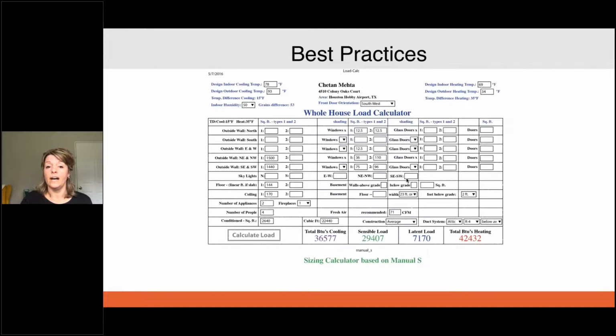So best practices for designing systems. We have our design indoor cooling temp and the outdoor temp, which is the peak load. So that design outdoor cooling temp is going to be the peak outdoor temperature that we're going to design our HVAC system around. And what's important to know about that is when we're using these best practices to design our AC system, typically those conditions are about 1% of the time. So we're designing systems that are going to run like we designed them 1% of the time. And then we've got to figure out how we're going to control, especially the relative humidity, the other 95, 98% of the time, 99% of the time when we're not at our peak conditions.